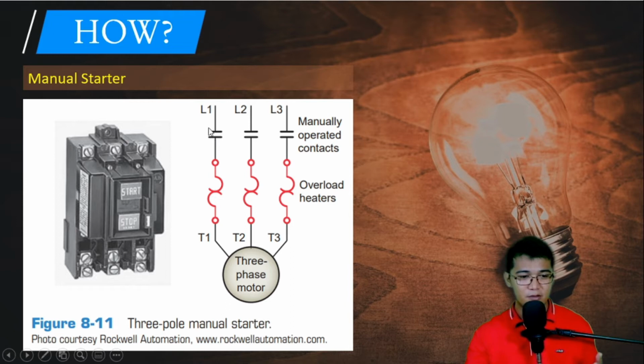Basically, we have the main contacts, normally open. The top is connected to the supply voltages, line 1, line 2, and line 3 - this is the three-phase AC voltage, connected at the top. Then at the bottom are connected our overload heaters, which disconnect or trip whenever there is overcurrent. After that is connected our three-phase motor.